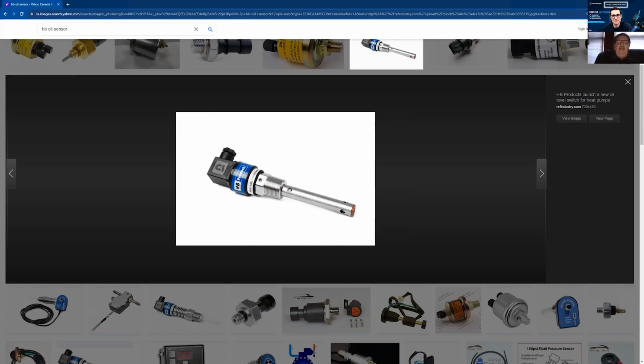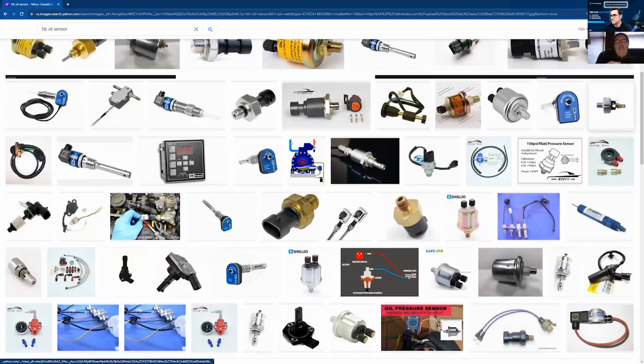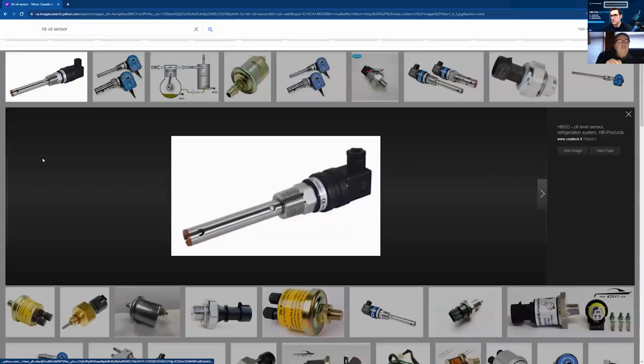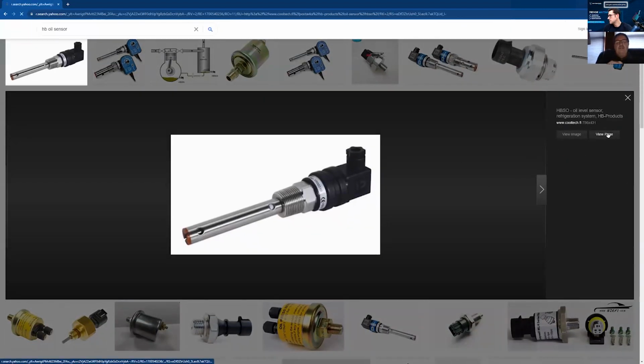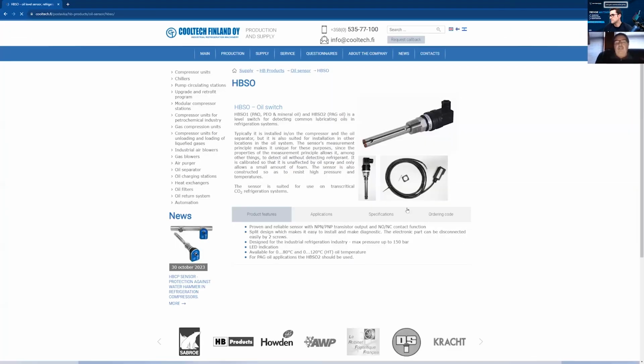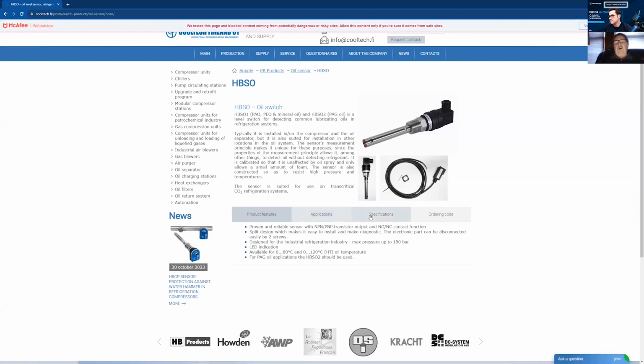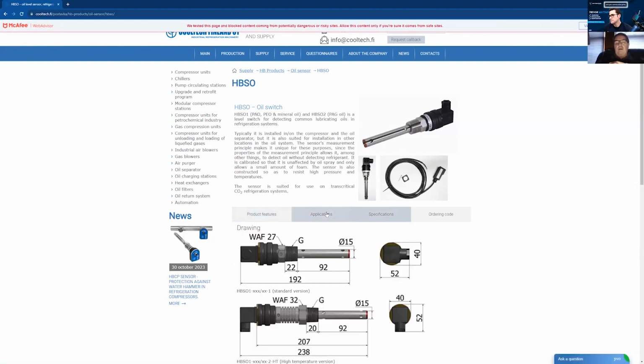It turns to red in the separator. That means we now have fluid going through these holes and making capacitance and making our switch. You have three wires. Number 1 is your 24 volt in. Number 2 is your common. And number 3 is your switch leg that comes out of that power head at the top.